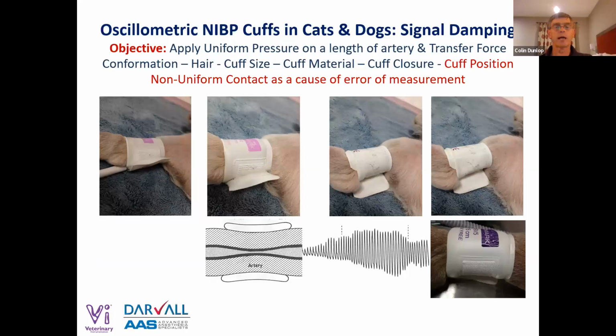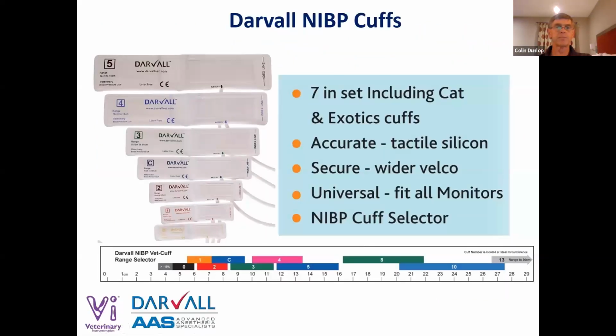When we put cuffs on, all I want to say about these cuffs is that the way that cuff inflates on the limb, the way it's positioned on the limb, has a lot to do with the transduction of pressure. So this one on the bottom right that is a soft cuff blows up like a sausage, so the force of this cuff is out, not down. What we want, when the cuff is positioned and inflated, is for that cuff to inflate as flat on the limb as possible. So then it's receiving the pressure from that length of artery up into the cuff, particularly when we're trying to measure these 1 to 2 millimeter of mercury oscillations.